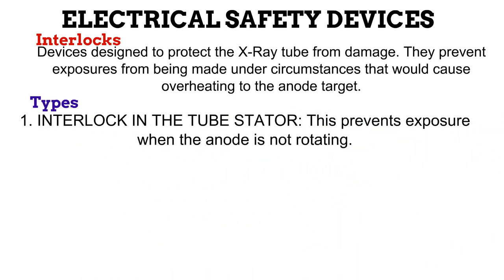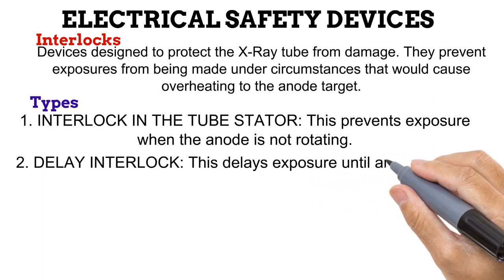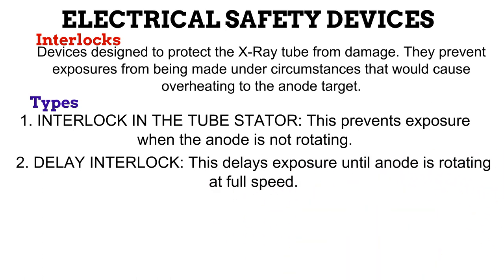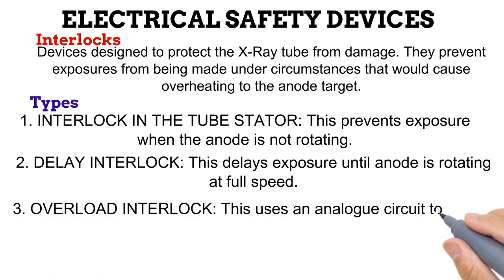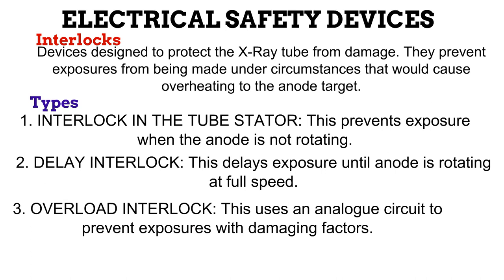The first is the interlock in the stator, which prevents exposures from being made when the anode is not rotating. The stator sets up a rotational magnetic field that causes the rotor to rotate; if there is a problem with the stator, the rotor and anode won't rotate, and creating exposures with a non-rotating anode can destroy it. The second is the delay interlock, which introduces a delay period before an exposure is made, enabling the anode to reach its full rotation speed of about 3,600 revolutions per minute before exposure. The third is the overload interlock, which uses analog circuitry to prevent exposures when too high factors such as kV or mAs are selected.